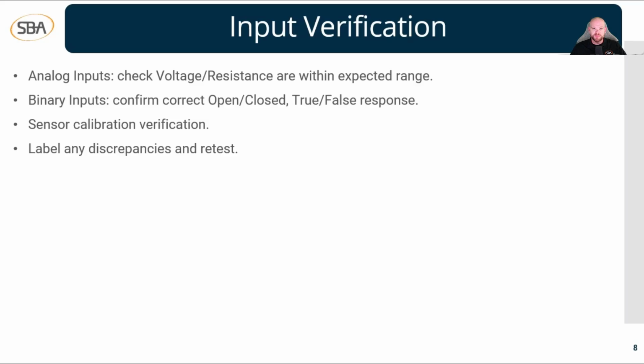So to start here, when we're talking about checking our analog inputs, there's a couple things we need to check here. We need to verify that our voltage or resistance are within the expected ranges. So again, our analog inputs are going to be things like temperature sensors, humidity sensors, CO2 sensors, things like that. So we're going to check our voltage and resistance readings to make sure that they're within those expected ranges.